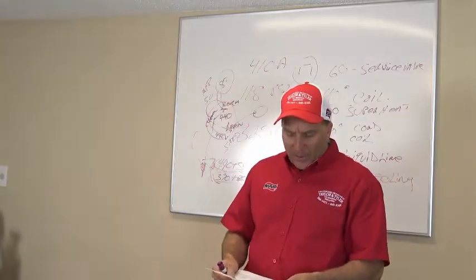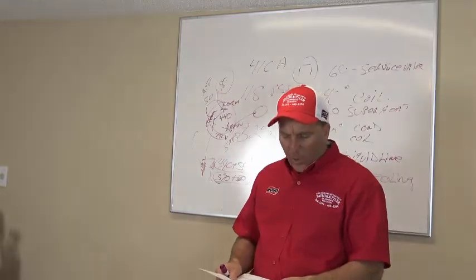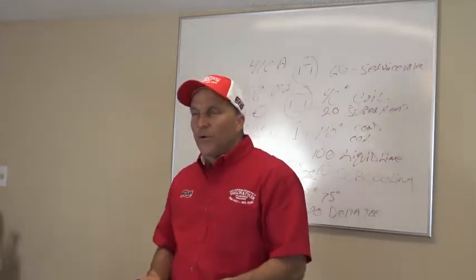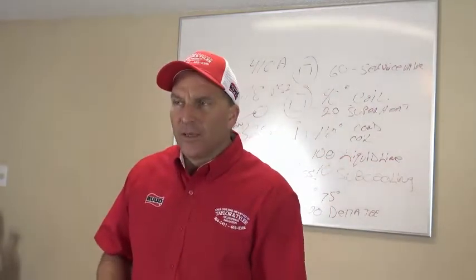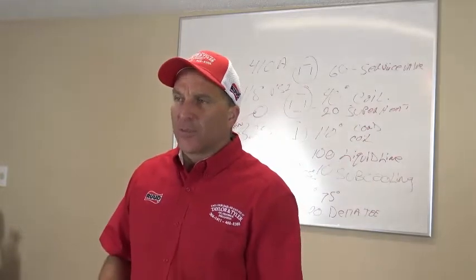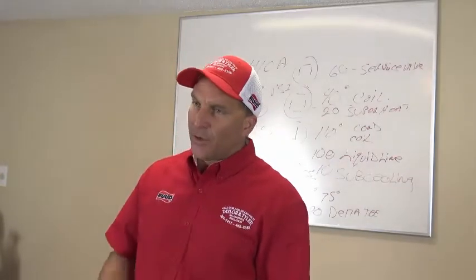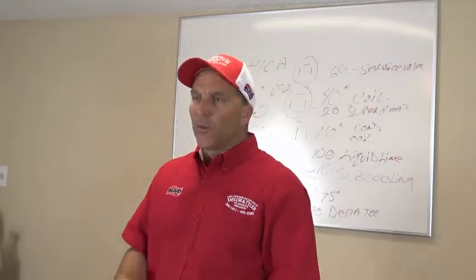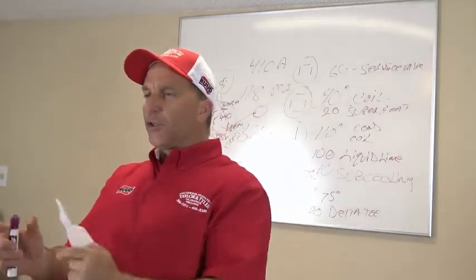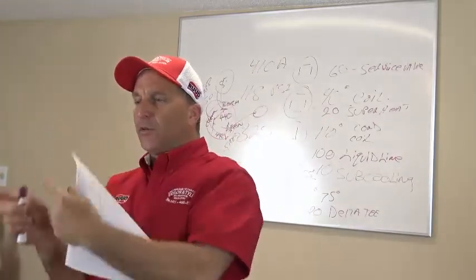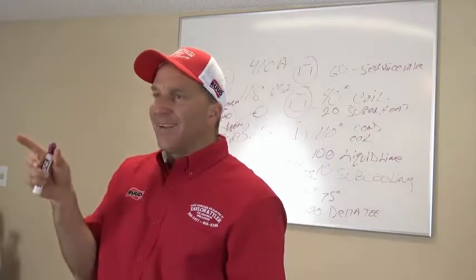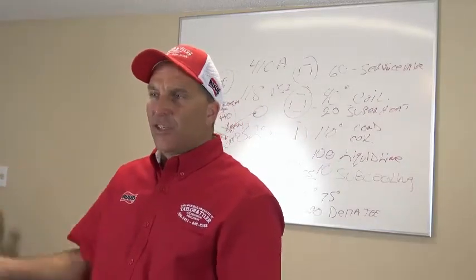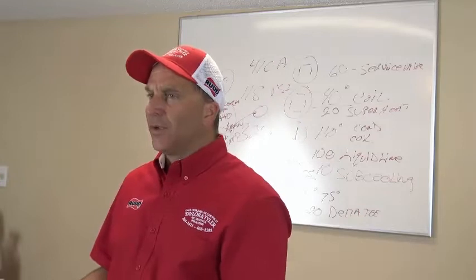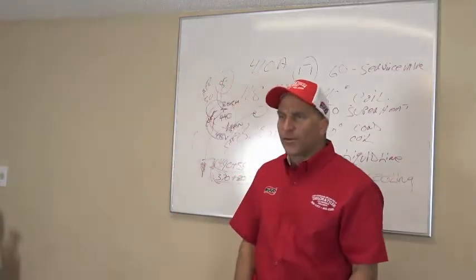So capacitor size, and then I want to know what the actual reading is. So if your reading says 42, then you should actually go to that customer and say, here's a price on a new capacitor. Your capacitor is reading 42. Bring the capacitor in there to them, put the meter on it, say, see, 42. See what it says? 50. Can they deny you? Can they tell you that you're lying, cheating, and stealing? No. You put your meter on it and brought it right over there to them.